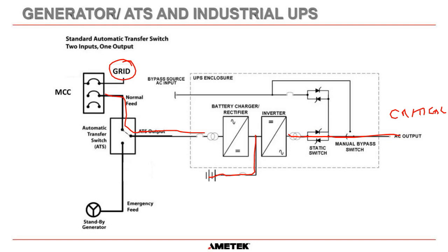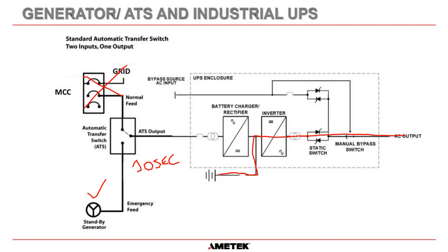And then what happens is if we have a power outage, the grid goes down, once again, the automatic transfer switch says, okay, start the standby generator. But during the 30 seconds or so it takes to start up, we have power from our battery through the inverter out to the load circuits. So we have continuous power. We do not lose power at the output to your AC distribution panel. And then once the emergency generator is up to speed, and after the 30 seconds, this contact here closes, and we automatically get the batteries back on charge again.